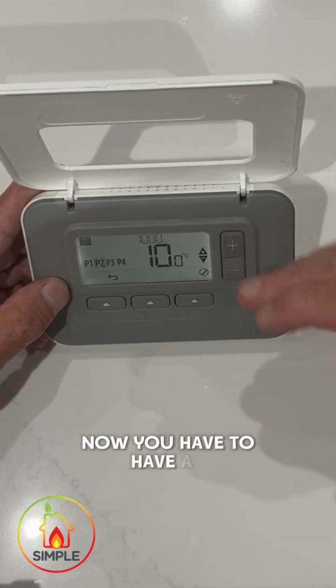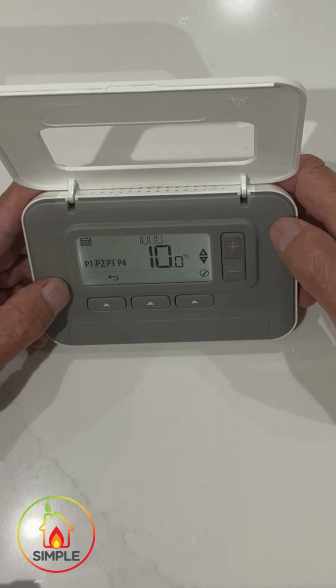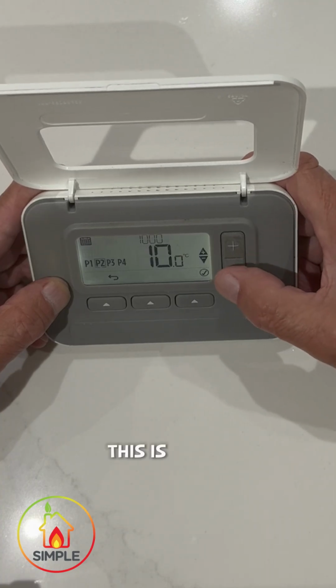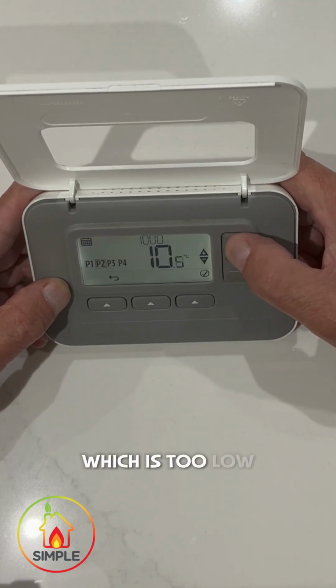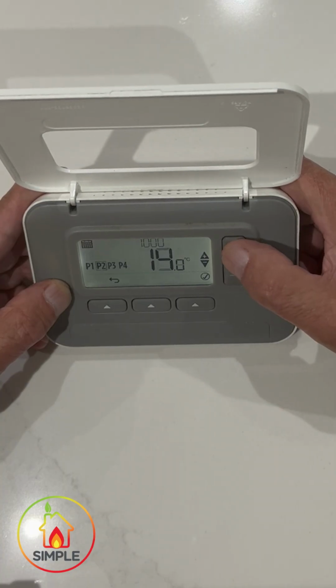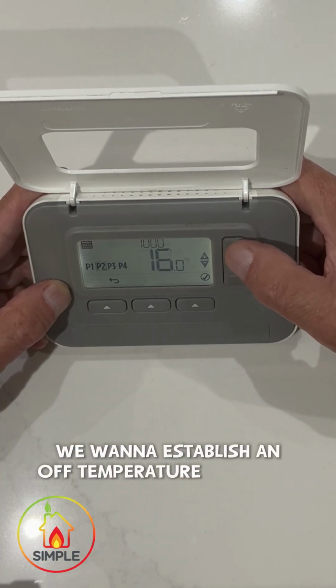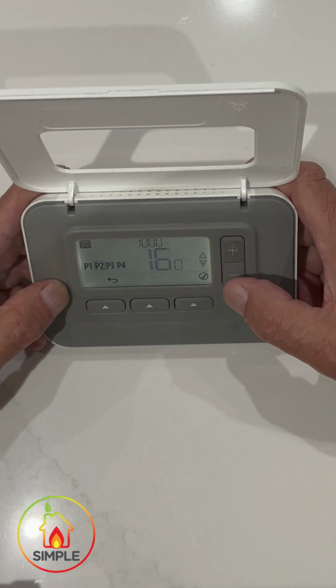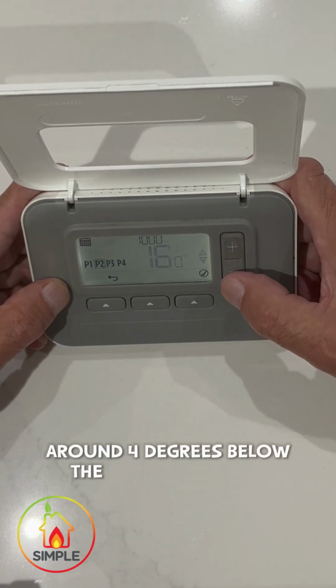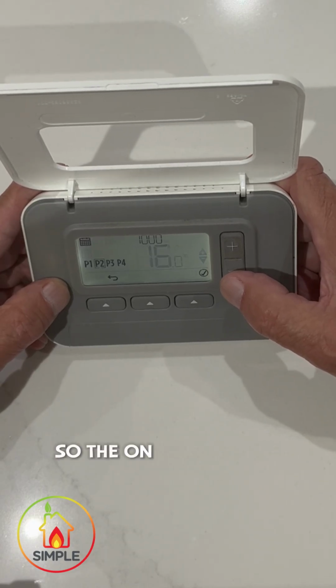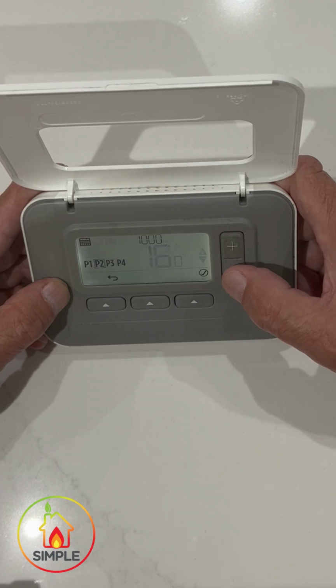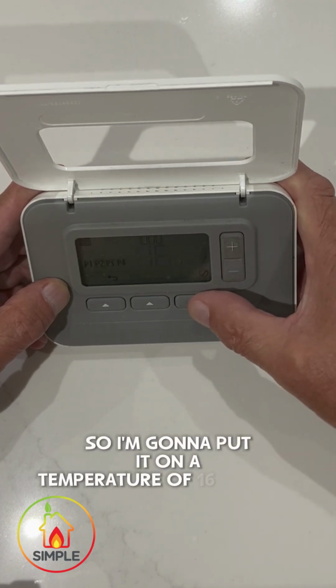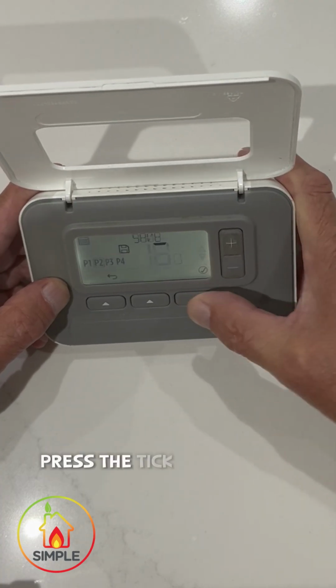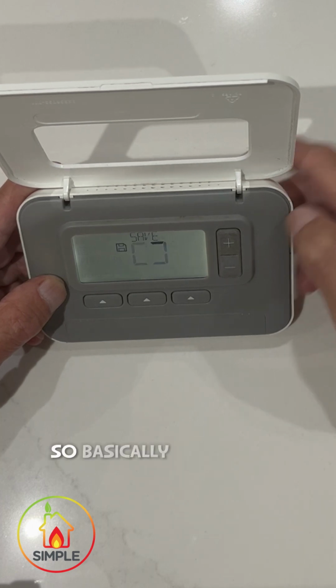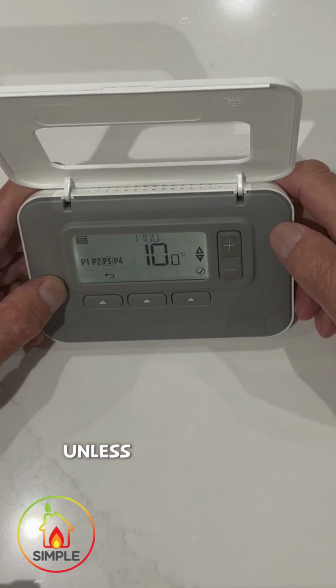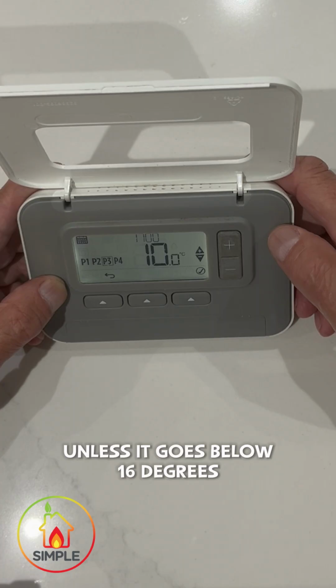Now you have to have an off temperature. This is set at 10 degrees, which is too low. We want to establish an off temperature around 4 degrees below the on temperature. So the on temperature I want is 21, so I'm going to put an off temperature of 16 degrees. Press the tick, that's saved. So basically, your heating won't come on unless it goes below 16 degrees.